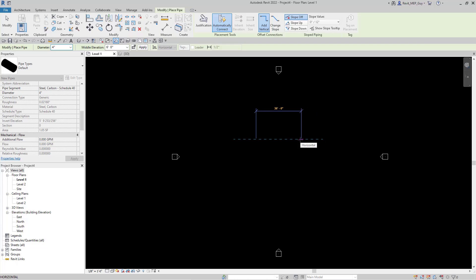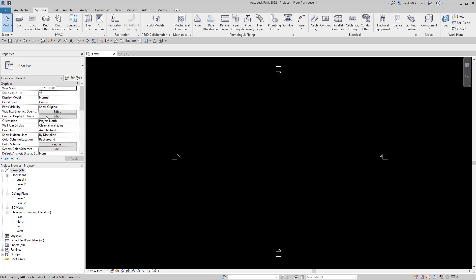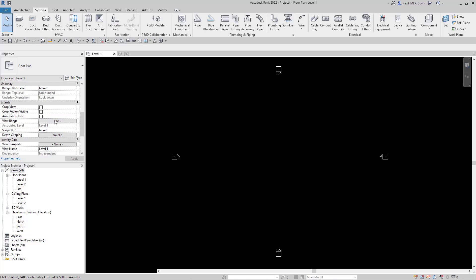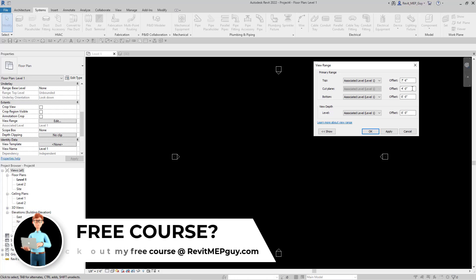The second thing you'll want to check is that you are in the right type of view, and usually the view is going to be displayed based on the discipline. When I go to Floor Plan and look at Discipline, you'll see it says Architectural. Architectural floor plans only display things that are below the cut plane. If I go back to my View Range, you can see there's a cut plane. For architects, this is used to display cabinets, windows, and certain things intersecting this cut plane, but anything above this cut plane is not going to show up — so all pipes drawn above four feet will not show up.